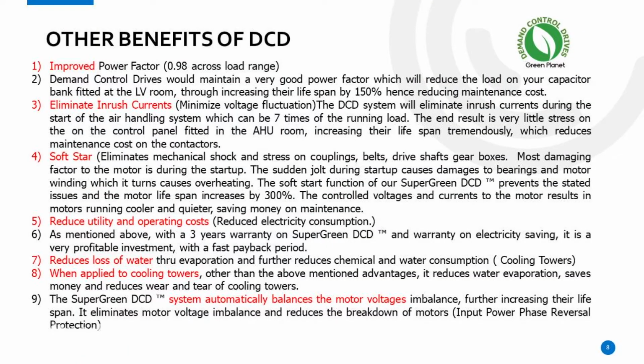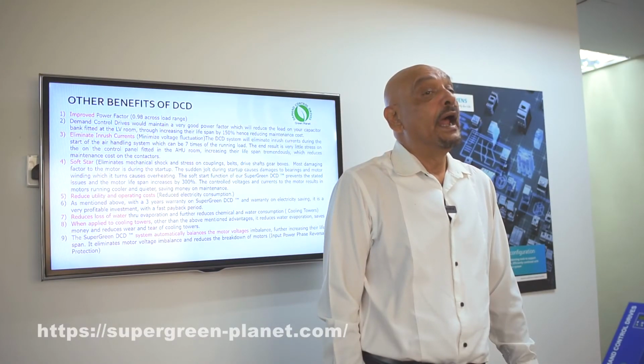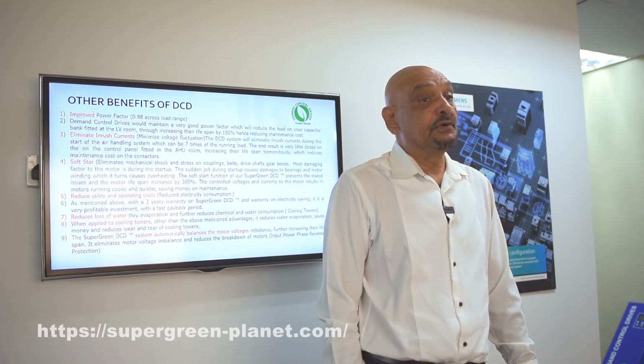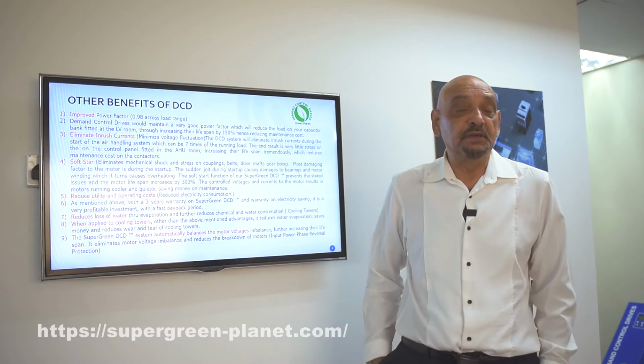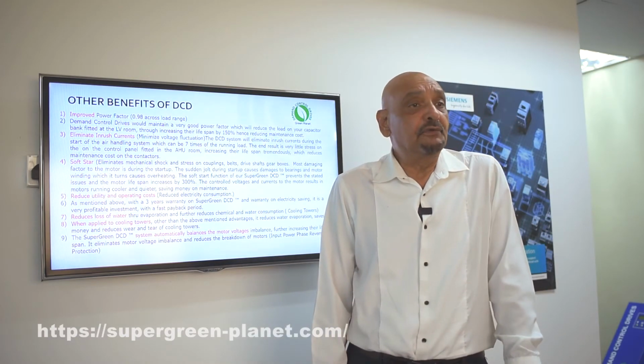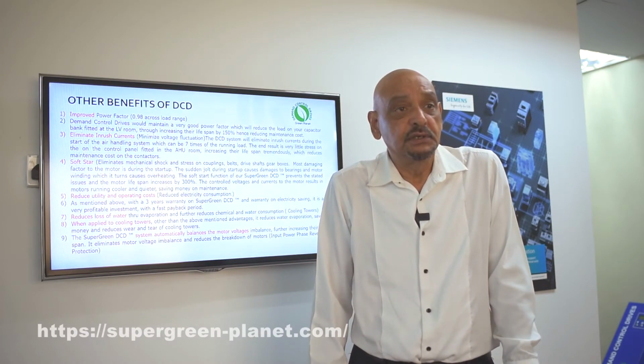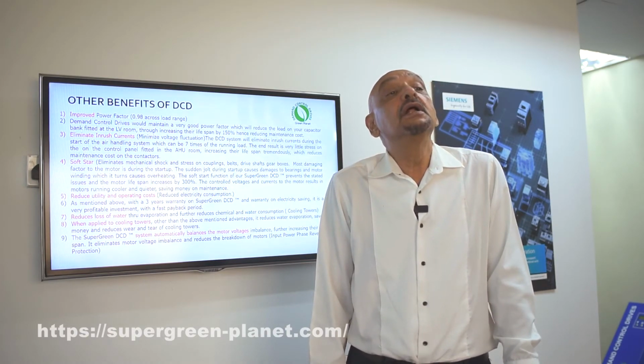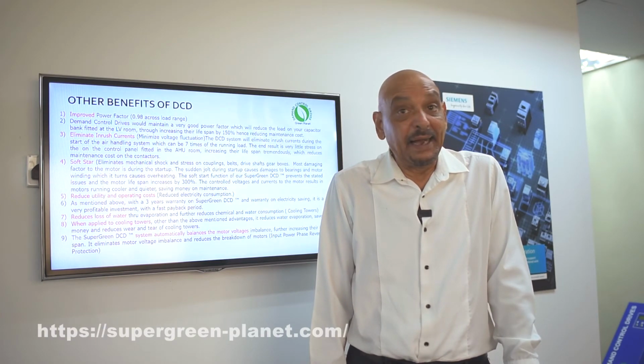Now let's look at other advantages which DCD is going to give you. For example, your power factor. Currently, in most of the locations where I've done the measurements, I found that at the air handling unit, the power factor is always within the region of about 0.5, even 0.4, 0.8. After we have installed the demand control drives, the power factor at your equipment level is automatically increased to 0.98 by the DCD system.